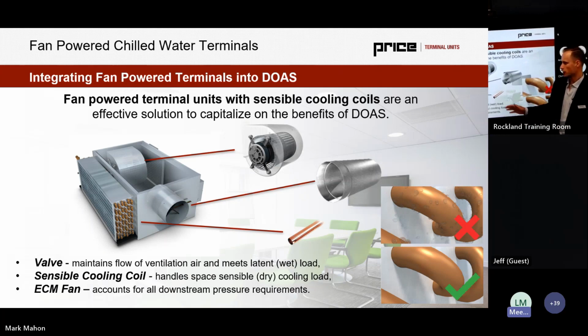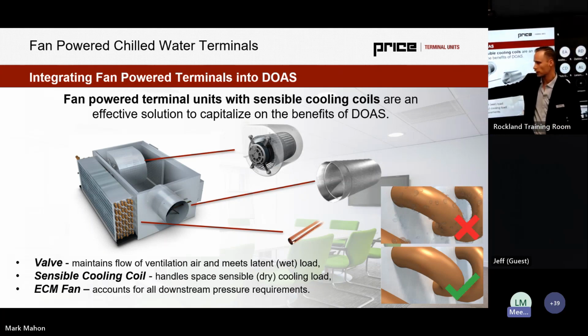The way this equipment actually works is we have our ventilation volume, which is usually about a quarter of the supply air volumes that we need for the space. The difference between the fan set point and the ventilation set point for the product is air induced through the coil, sensibly cooled through the coil, mixed with the ventilation air so we can still supply anywhere from 55 to 60 degree Fahrenheit air into the zone for design day cooling. Any questions on this product?